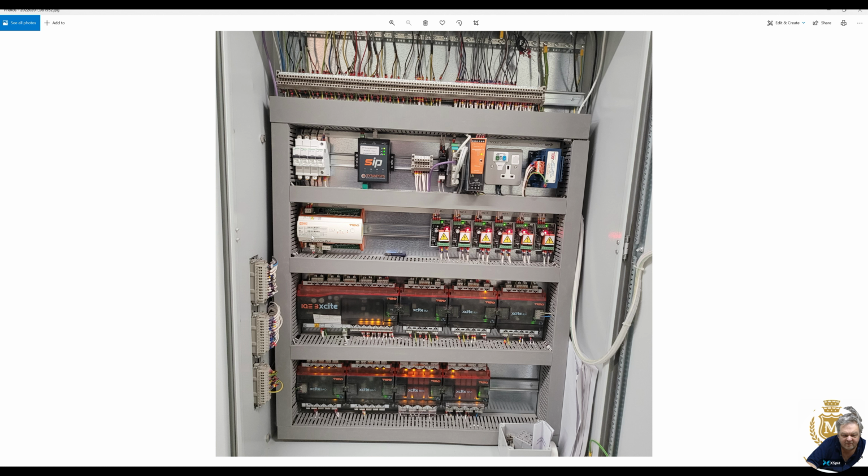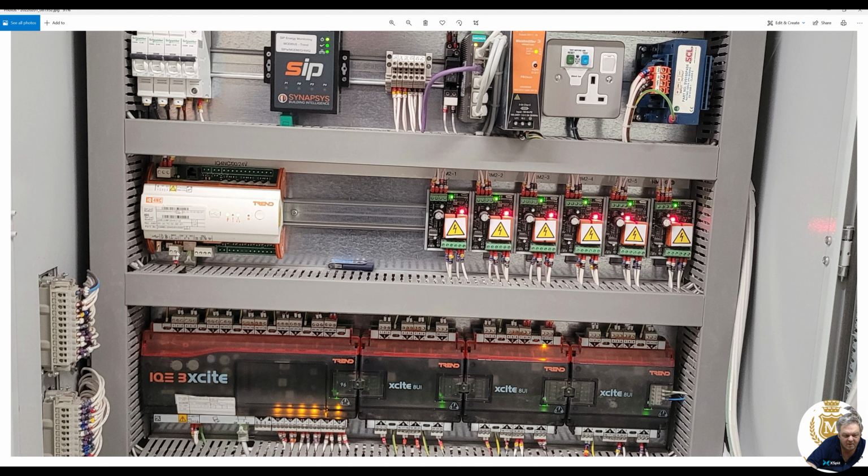Now the reason this is being used is for BACnet. These 2 connections here are MSTP BACnet out to all the devices in the building. They are fan coils and manifolds, and then this Ethernet connection here is connected back to the switch, and we pick up via the IQ3 via BACnet through this device, this IQ4NC.